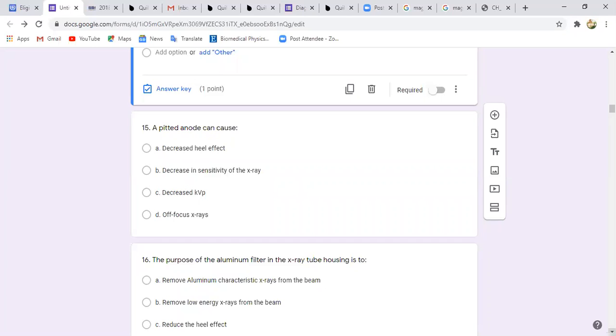Of course, this is usually an issue with stationary anodes. But most times, what we have is rotating anodes in so many of the X-ray machines, except for fewer ones like the mobile X-rays that can still make use of a stationary anode. Because of course, we are looking at the volume of work there. They usually use it once in a while, maybe 10 exposures in a day. It can be used in a very, very large hospital. That will just be one of the two.